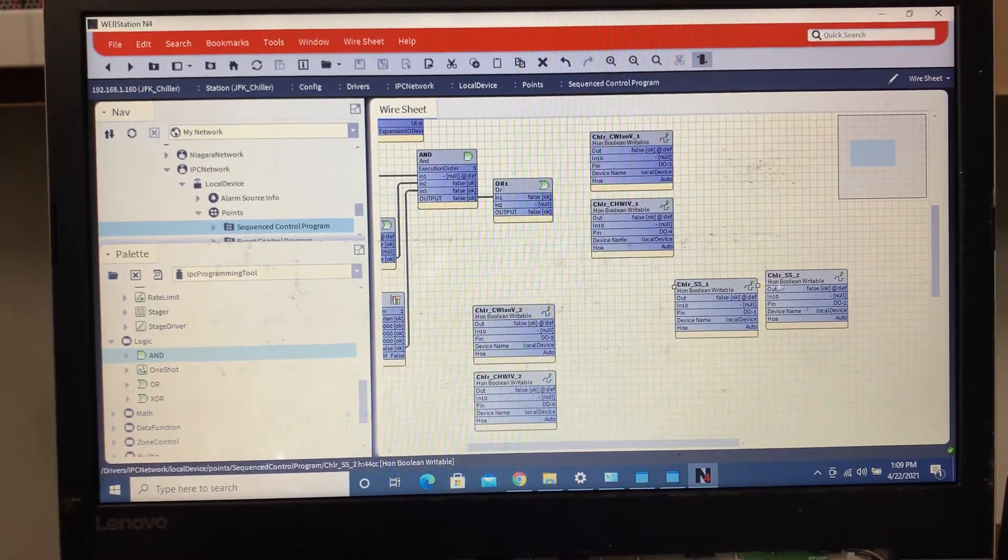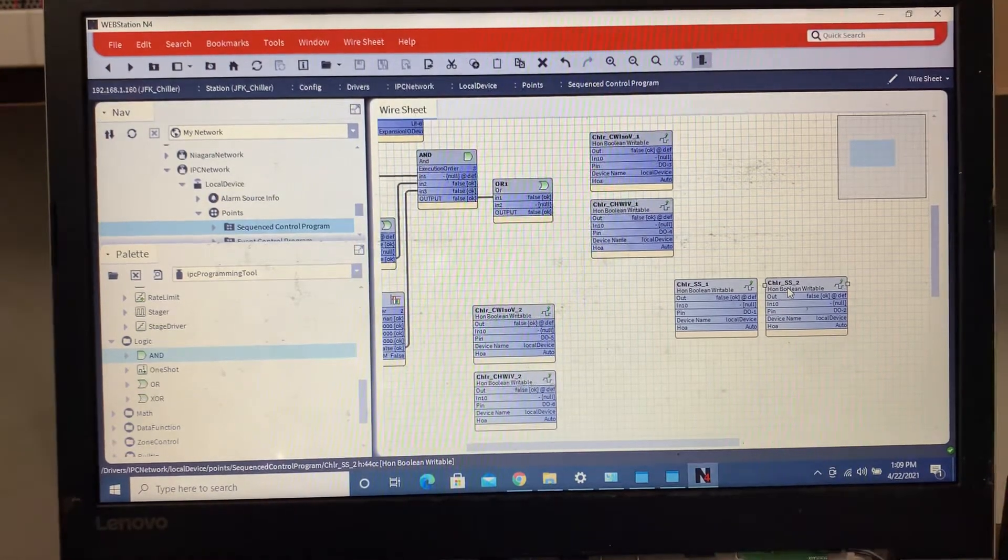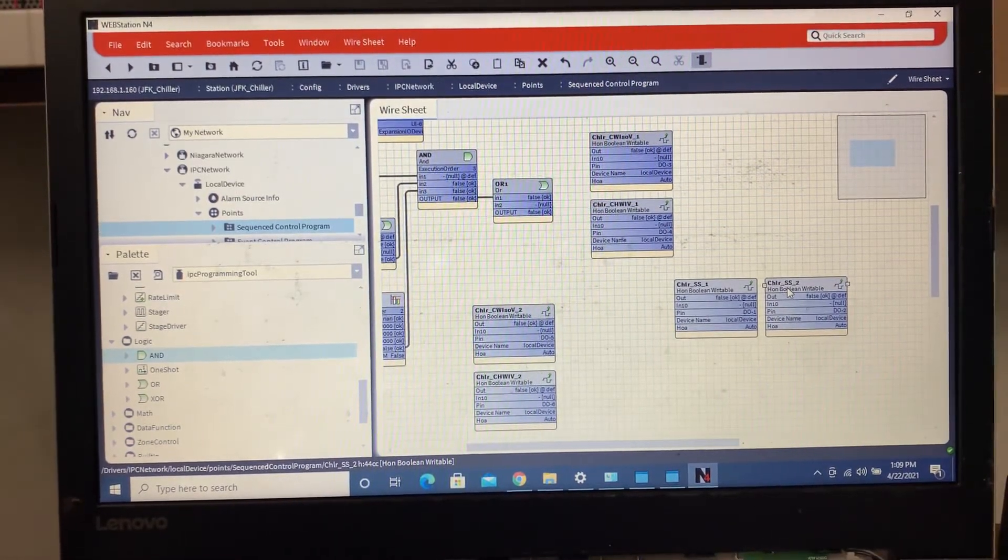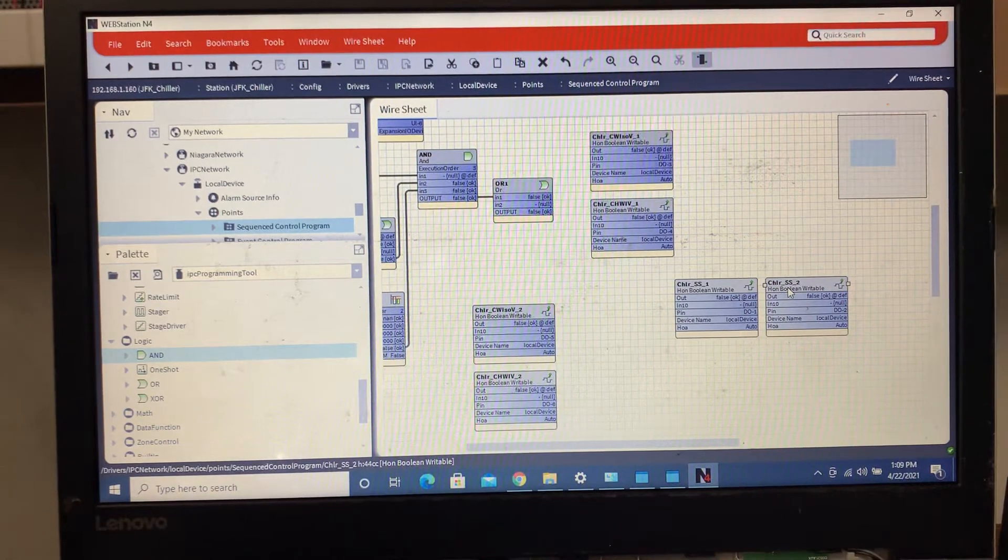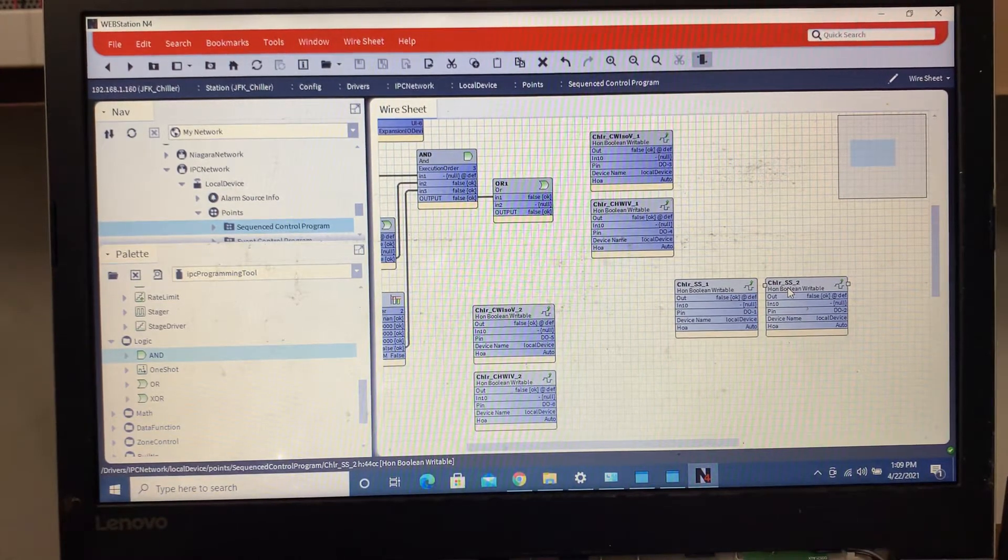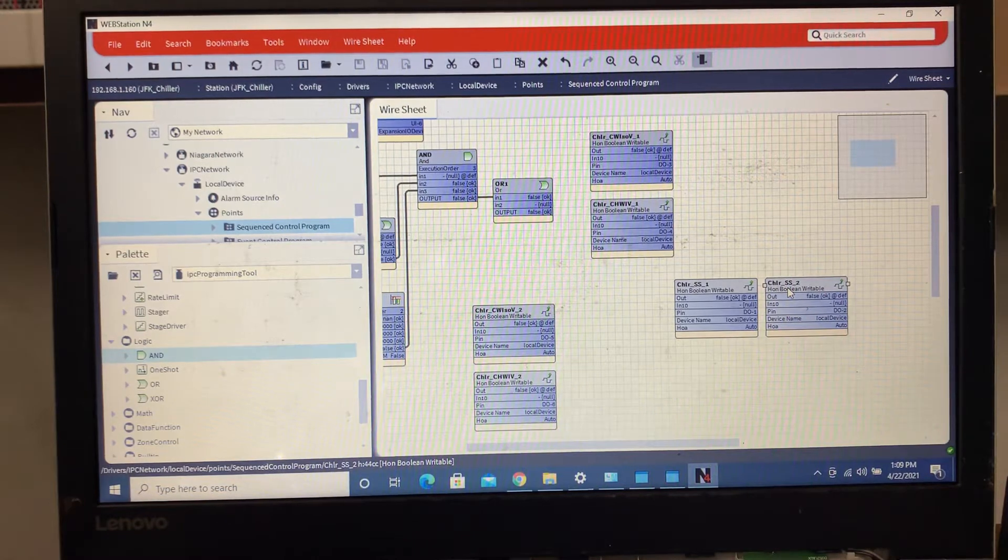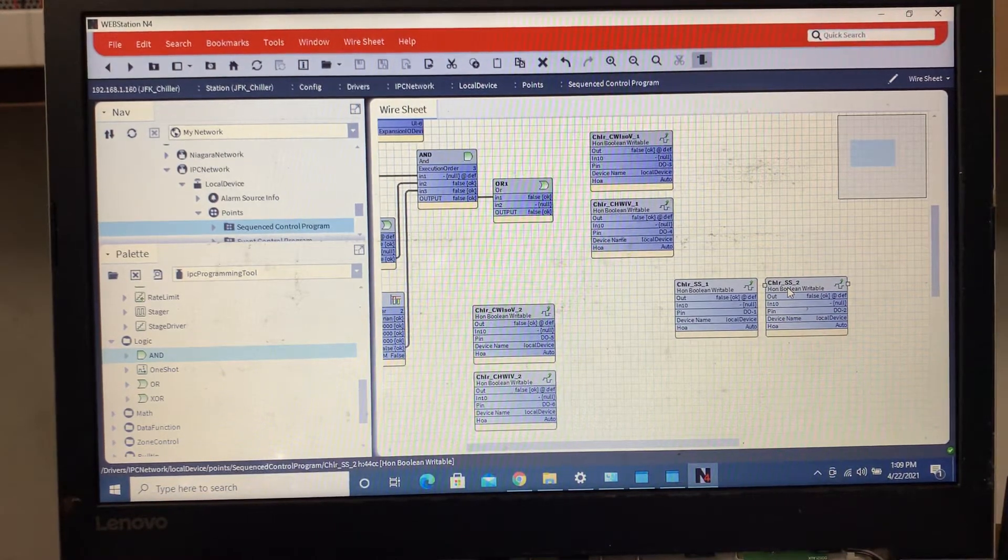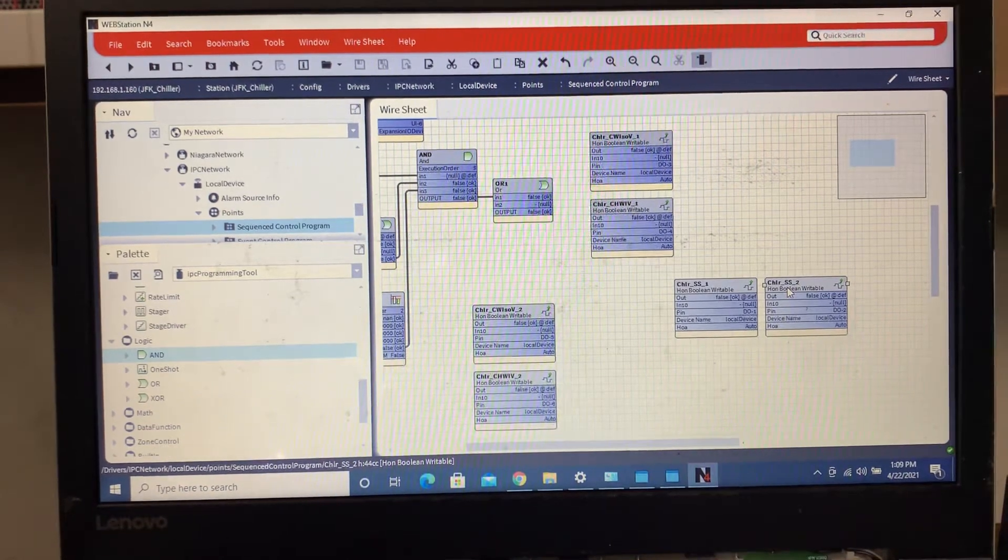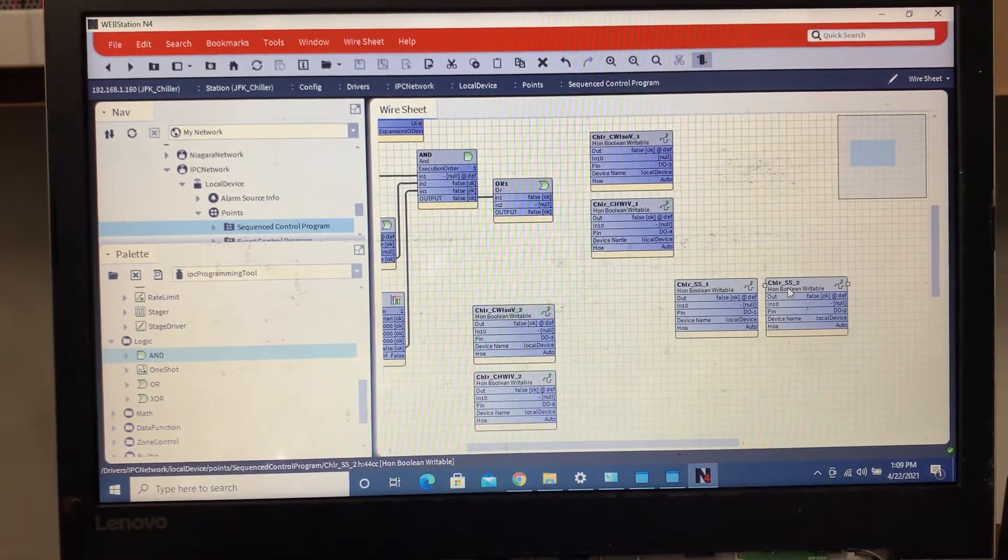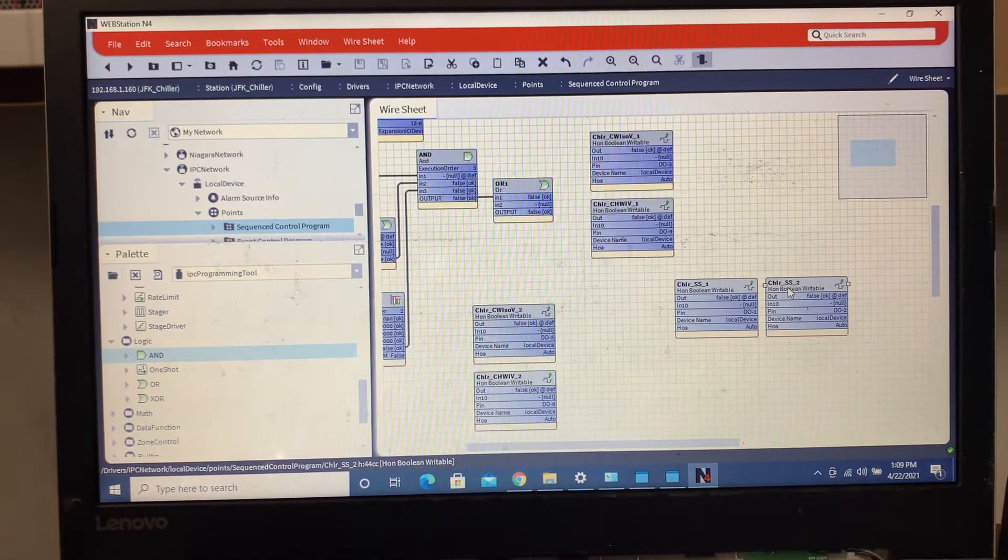Everybody's kind of got their own way. It just depends on how the engineer has designed it. If he's done it based on a delta T between supply and return, if the return starts getting above a certain temperature or the supply. Let's say they're maintaining, they're trying to maintain 42 in the building, but the temperature starts getting up to about 50, and then that's when they usually want to bring on a lag chiller.